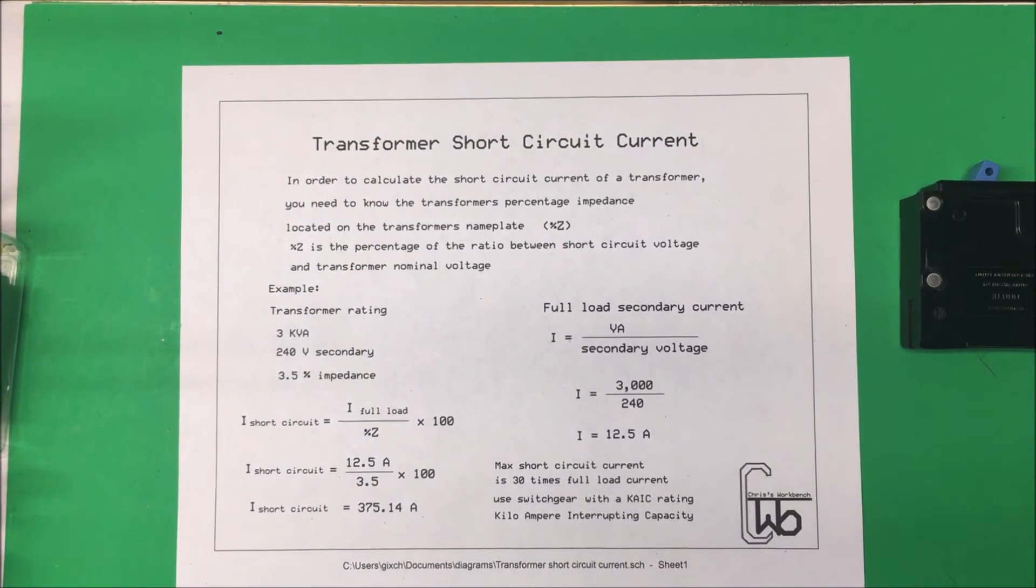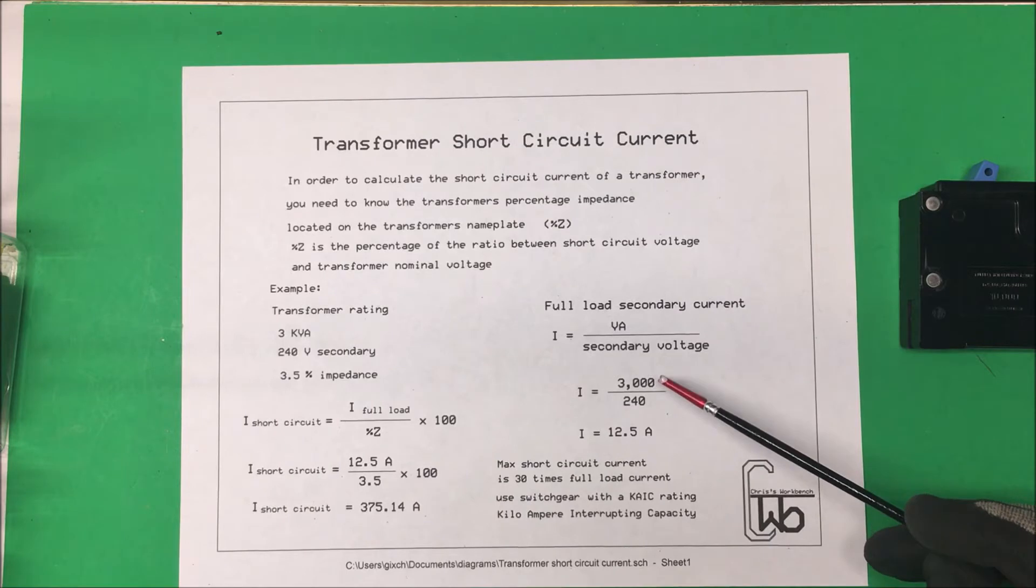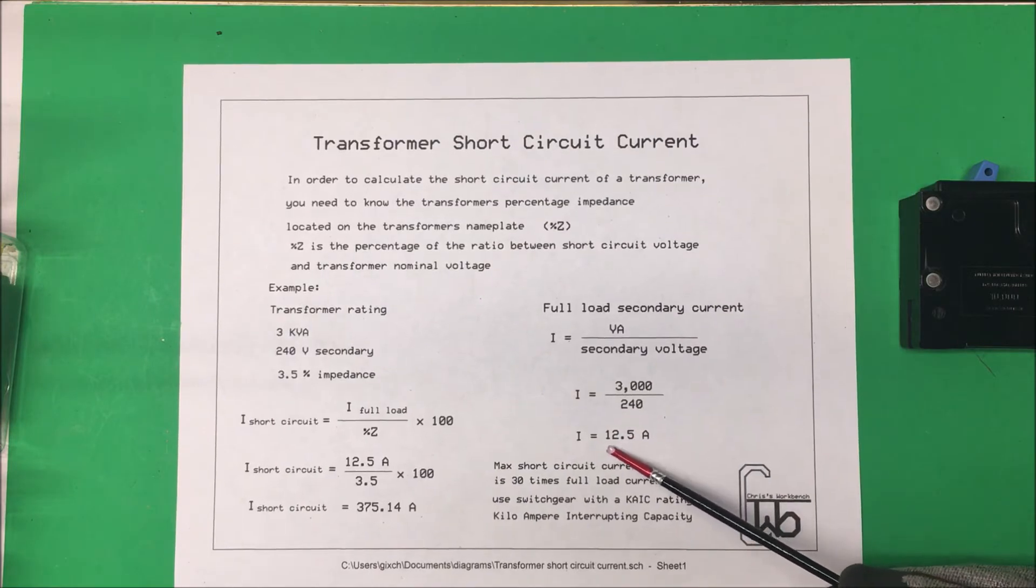To calculate our full load current, we just take our secondary voltage, which is our 240 volts, and we divide that into our VA, which is 3000, so it turns out to be 12.5 amps. So this transformer is good for 12.5 amps on the secondary.